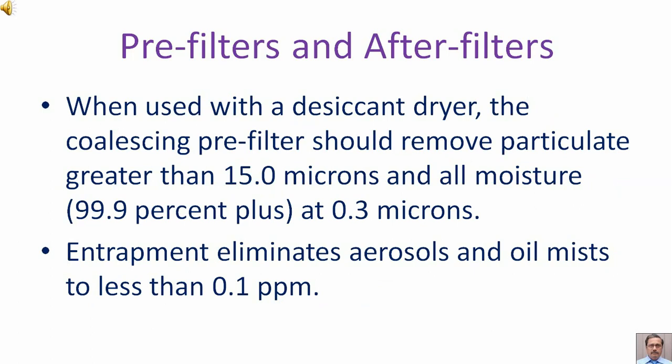When used with a desiccant dryer, the coalescing pre-filter should remove particulate greater than 15 microns and all moisture — 99.9%+ at 0.3 microns entrapment — eliminating aerosols and oil mists to less than 0.1 ppm.